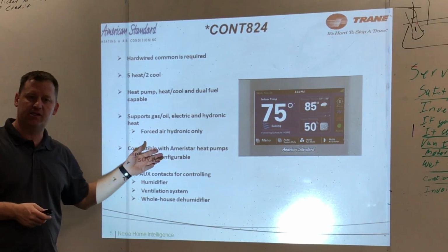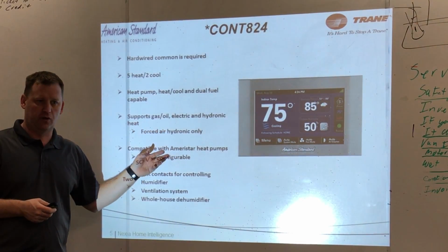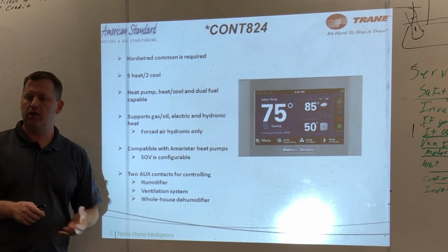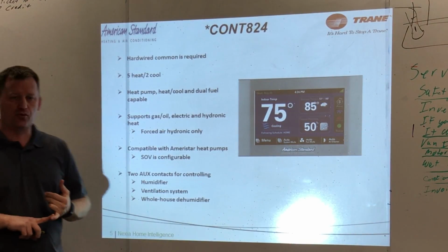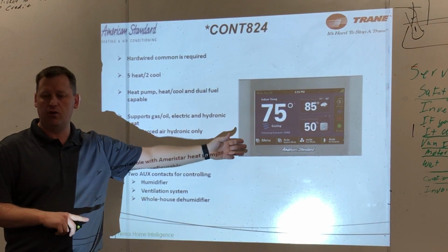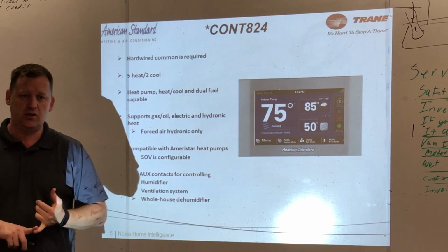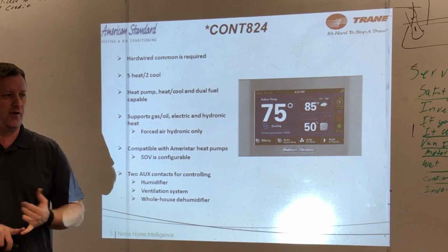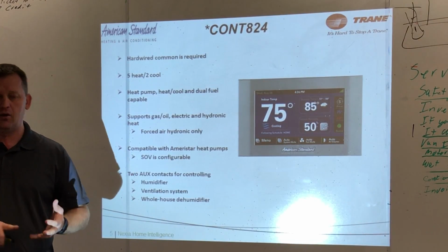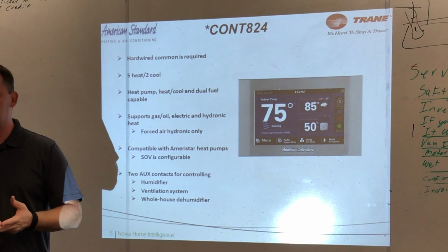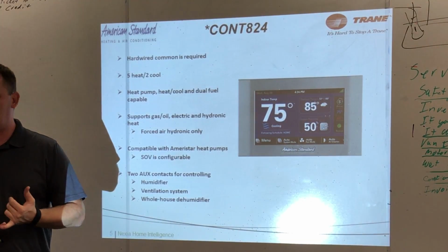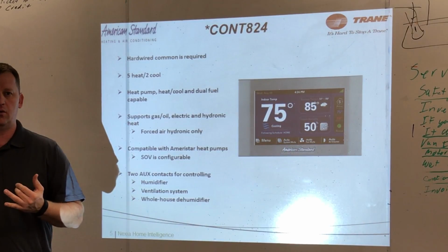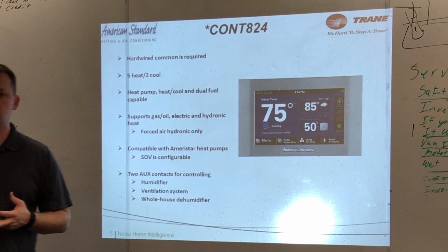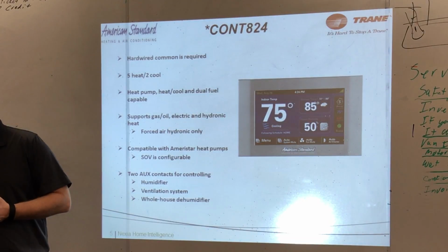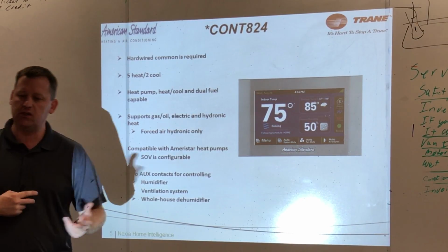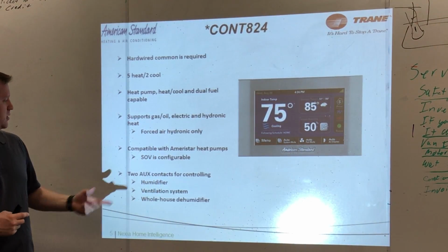You can use this as your service stat. Instead of using the 8320, you can use this 824, because you can tell it the switchover valve is energized in cooling like a Trane, or energized in heating like a Marshall, York, Coleman, Rheem, Ruud, or others I can't remember. Some geothermal systems do that too. So it gives you the ability to use this on anything.